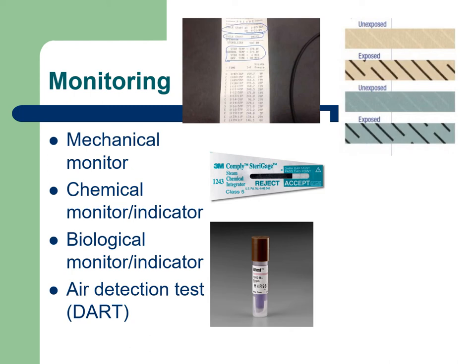This biological indicator is going to be placed in every single load that is run in the steam sterilizer. When the load is done, this biological indicator is going to be retrieved. The information, the date, the sterilizer, whatever, is going to be written on here. The cap is going to get pushed down. That is going to activate the food. If you can see right at the bottom of the purple, it's little whitish. That is spore food.